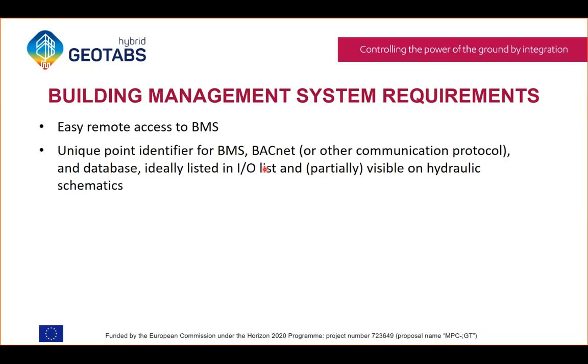Another painful point we discovered during the project is that the different measurement points and control points don't have a unique identifier. There's a different identifier in the BMS than on the BACnet layer, than on the database. So it's a whole puzzle to find out which point is which.